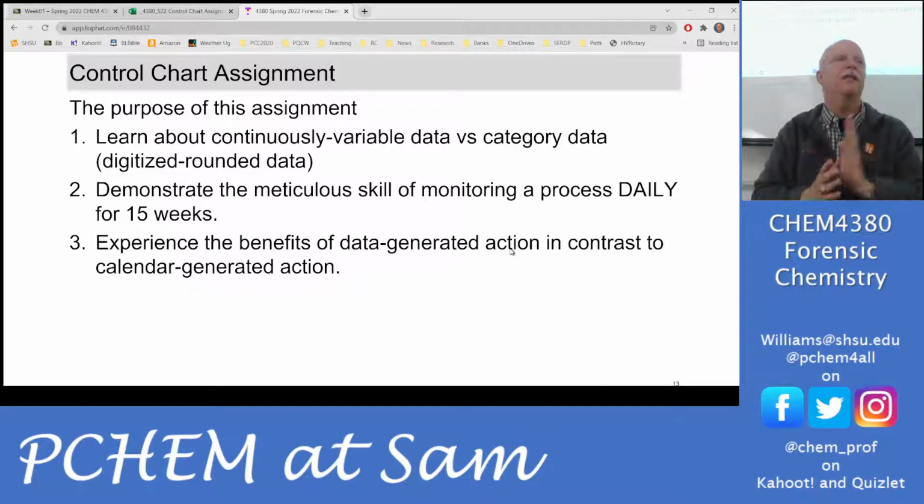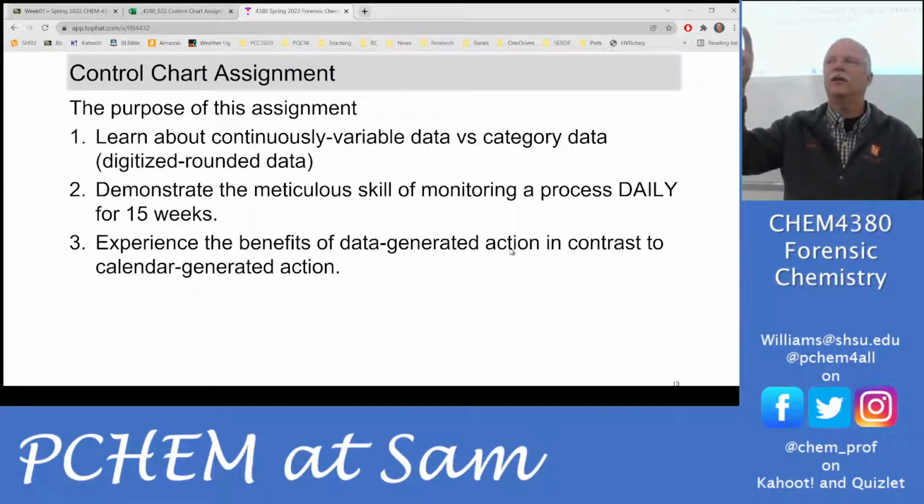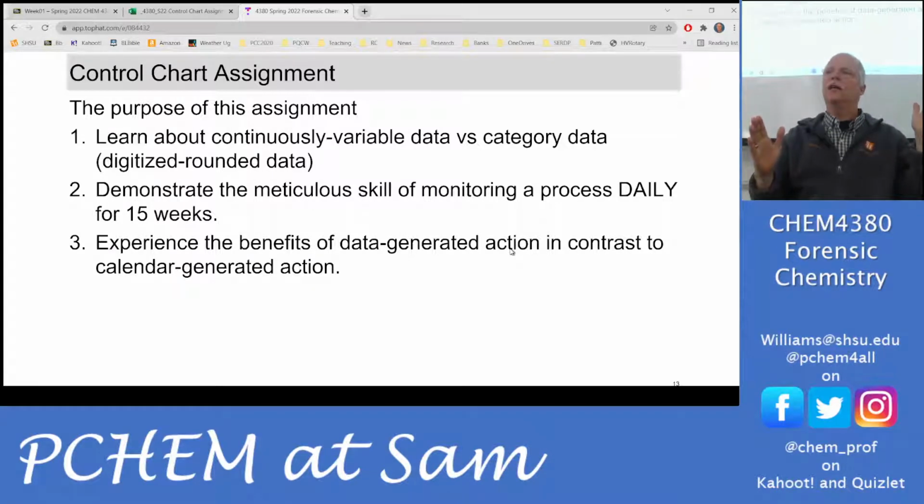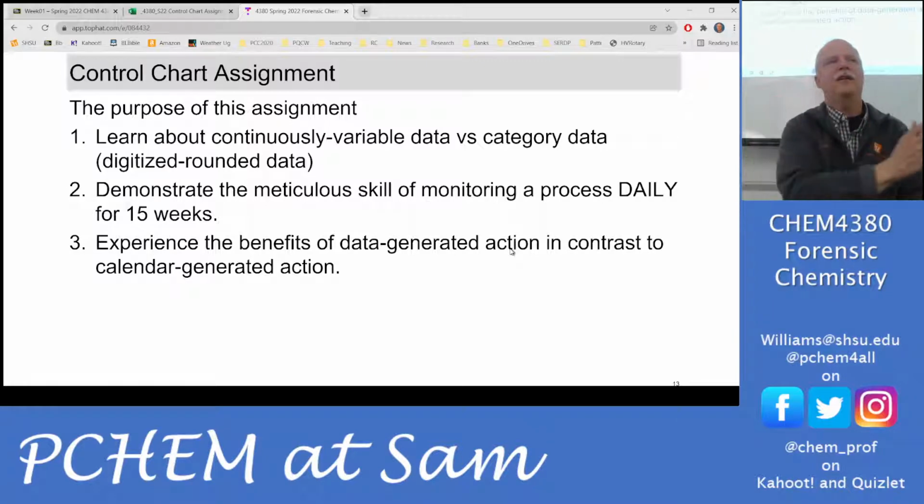You could track that retention time and put that on a control chart. And then next day you put the next data point, next day you put the next data point. Third day, it's now all of a sudden missing, or it's stuck in the instrument a lot longer. It was 30 seconds late coming out. Something's changed, right? Now, you only know it changed if you know how it behaves day after day.